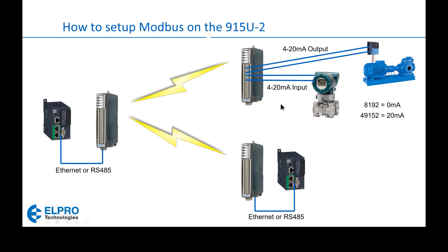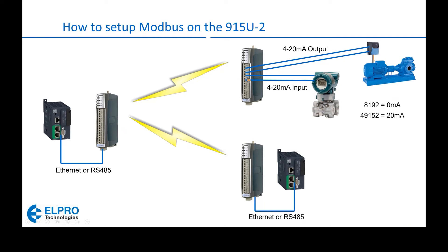At remote sites we can have this master radio map its data to analog outputs to control something like a variable frequency drive. Similarly we can have an input from a 4 to 20 milliamp pressure sensor wired into this radio and have that wirelessly mapped over here and then read using Modbus protocol by this PLC.